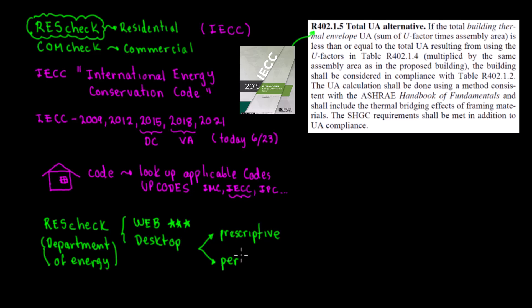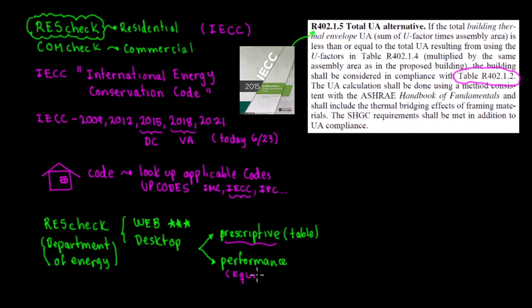The two compliance paths in ResCheck are prescriptive and performance. Prescriptive is essentially a table — specifically Table R402.1.2 — which indicates the minimum insulation values for the building envelope. The performance method also includes equipment, such as the HVAC equipment efficiency.